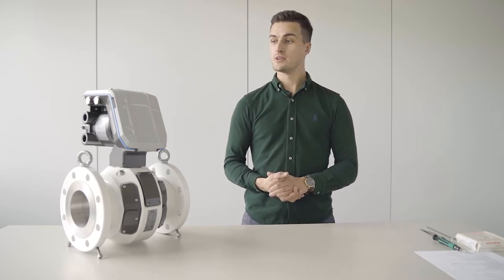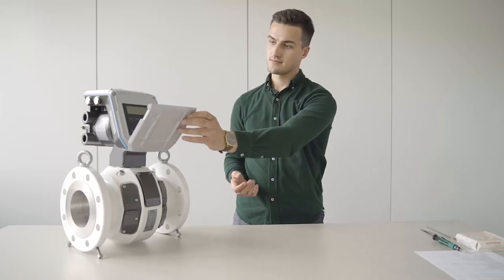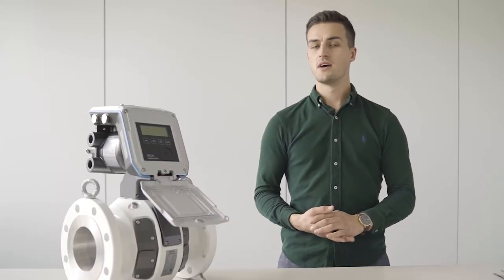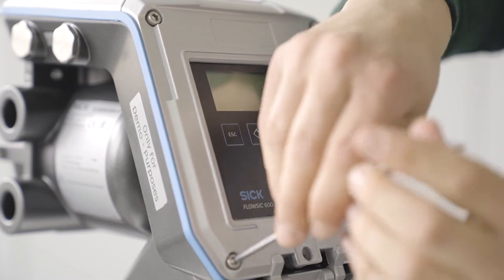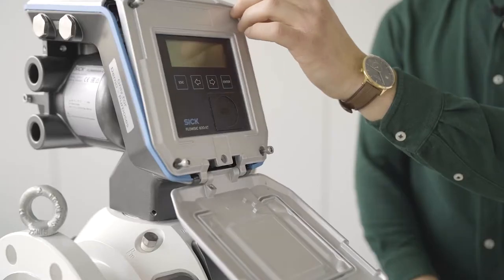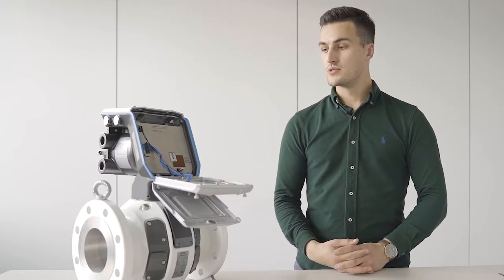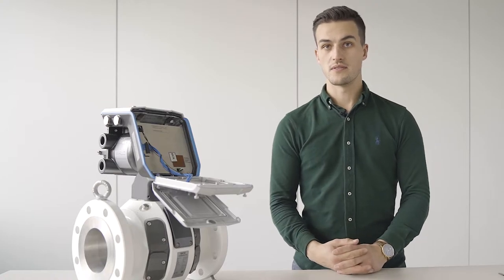First of all, we will need to open the display cover. After that is done, you are facing four screws which need to be loosened to open the display unit. Now you have to swivel down the display unit and you will face a metrological seal which covers the protection lock of the device.